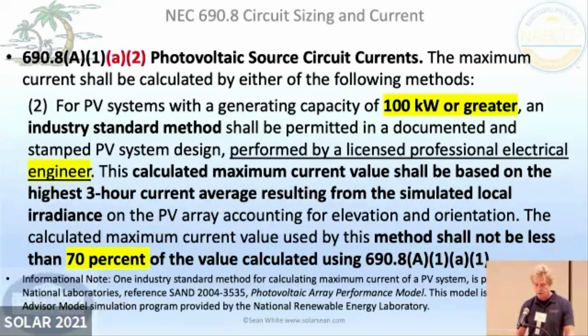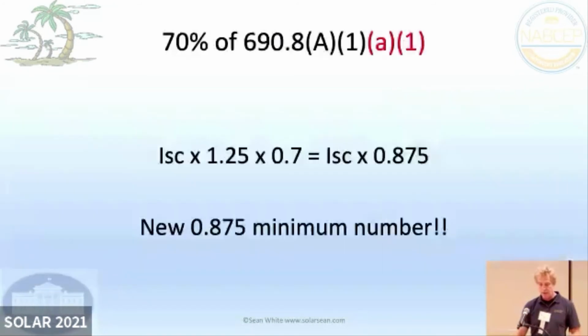One of those things too, if it's 100 kilowatts or greater and you got an engineer to supervise it, you can actually use 70% of what you were going to use. So it's like I give it this 1.25, but then I can shrink it down again. So there it is, short circuit current times 1.25. And then you bring it back down to 70% of that. So really it's short circuit current times 0.875, the least amount of current you could call it.